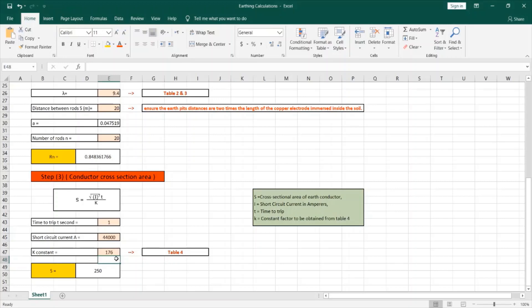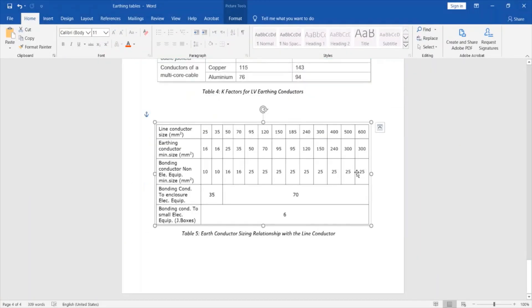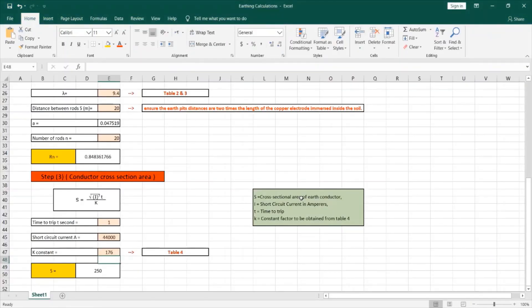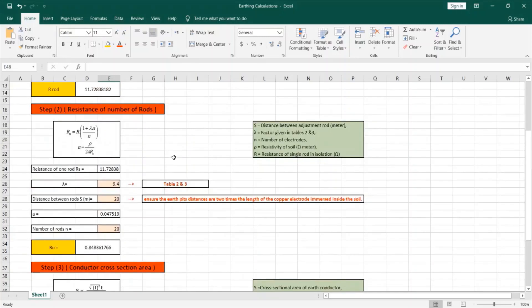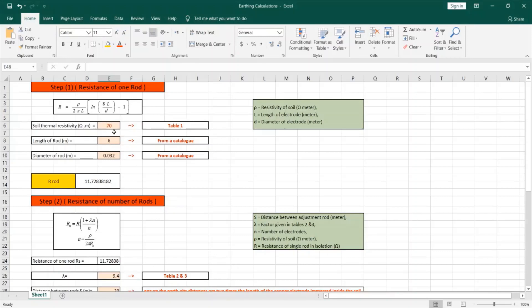As mentioned, you have the choice to size the earth conductor either using this formula or by using the table based on the phase conductor size, which is also included in this reference file. In summary, we have calculated the resistance of earth rods and applied the trial and error method to reach the target resistance of 1 ohm for a low voltage system. The next step will be designing the system earthing in AutoCAD, using the values obtained — for example, 20 earth pits around the building with a spacing of 20 meters between each pit.